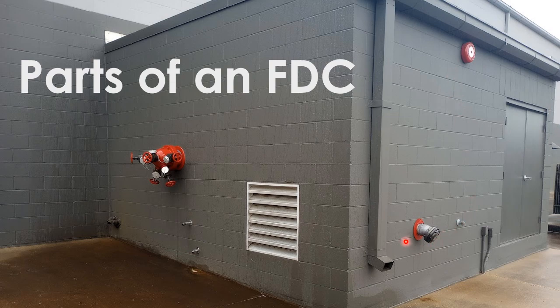And down here we have the fire department connection. This one is a Storz fitting to what appears to be a larger size pipe. If we're flowing into this building, the connecting pipe will be on the discharge side of the fire pump. In case there is a problem with the fire pump, the fire engine can take its place and supply the system, the sprinkler system. You may also have a standpipe system, but being what appears to be a single-story tall ceiling structure, there's probably not a standpipe system.